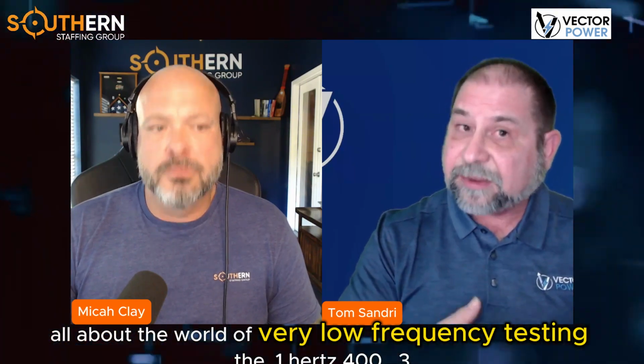So 400 basically just talks about testing in general and gives a preview of all the emerging and new technologies. Then it was broken off—400.1 talks specifically about DC testing, but now only for laminated dielectric type cable structures. 400.2 introduces us to the world of very low frequency testing at 0.1 hertz.